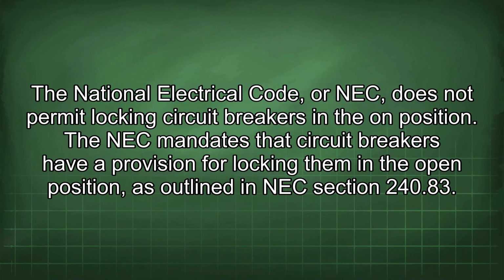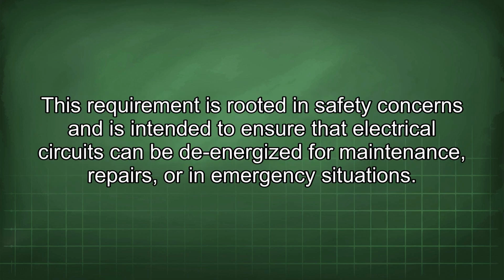The National Electrical Code, or NEC, does not permit locking circuit breakers in the on position. The NEC mandates that circuit breakers have a provision for locking them in the open position, as outlined in NEC section 240.83. This requirement is rooted in safety concerns and is intended to ensure that electrical circuits can be de-energized for maintenance, repairs, or in emergency situations.